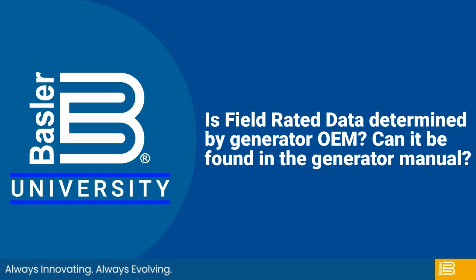Field rated data, is it determined by the generator OEM? Can it be found in the generator manual? Yes. Again, normally you have that field rated data, the full load field rated data, on the generator nameplate. It might be typically labeled as exciter field, but it is very uncommon to have the no load values.